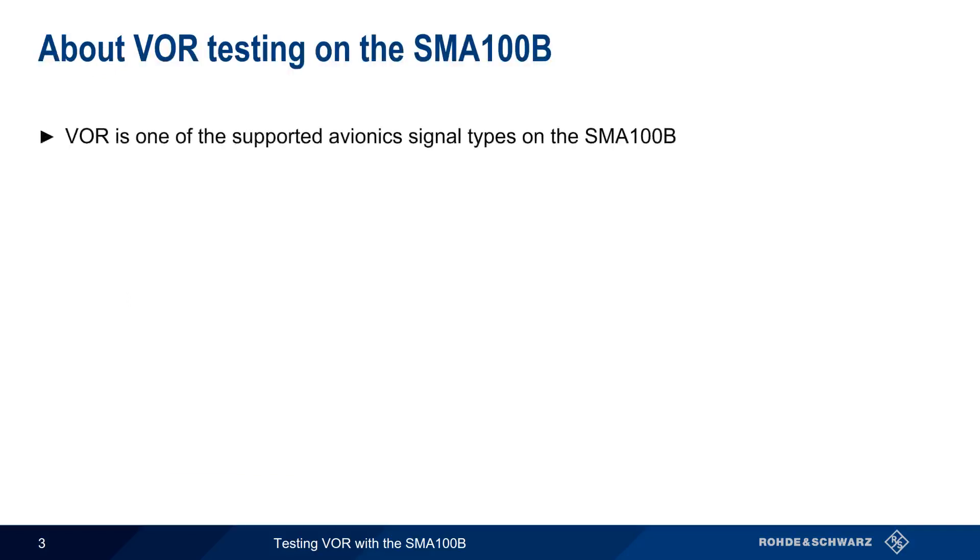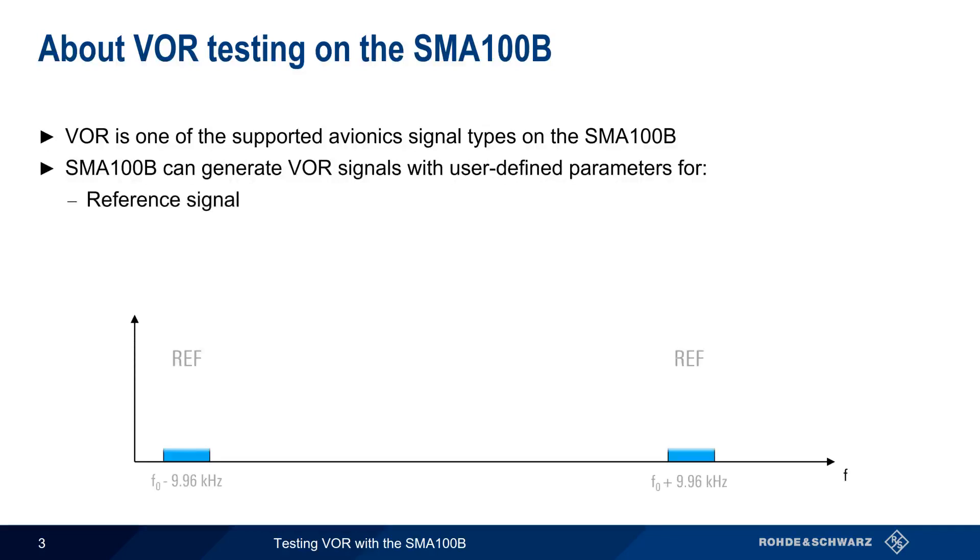VOR is one of the supported avionic signal types on the SMA-100B. In other words, the SMA can generate VOR signals with user-defined parameters for the three components of a VOR signal, namely the reference signal, the variable signal, and the COMID signal.